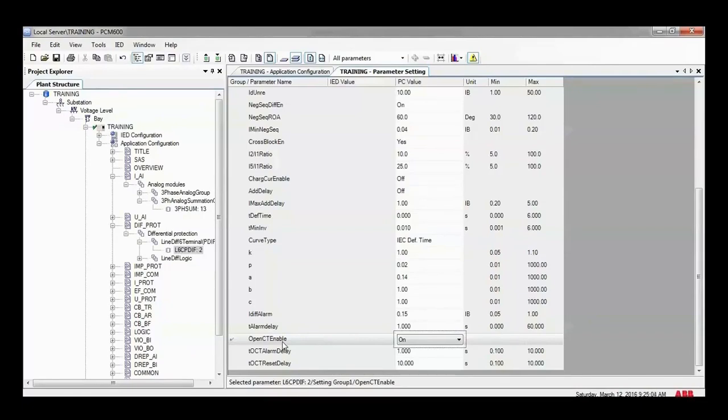After 50 seconds, it must also see that the currents are from 0.1 to 10. I'm telling you, I'm still explaining the scenario. The scenario tells you that you must see that your bias currents are greater than 10%, up to 10% of your float current for a duration of 50 seconds, and then the phase drops to 0, while the other two phases remain the same.